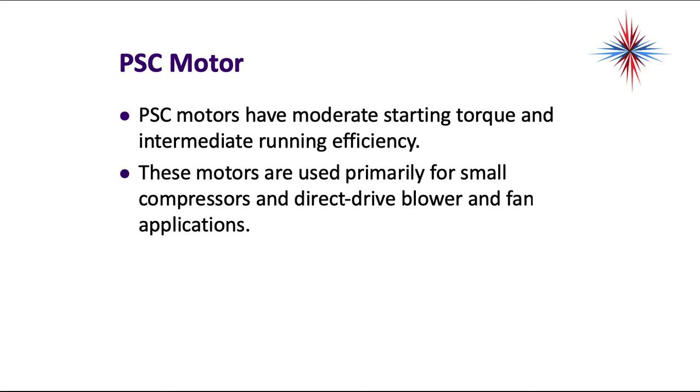PSC motors have a moderate starting torque, intermediate running efficiency, and these motors are used primarily for small compressors and direct drive blower and fan applications.